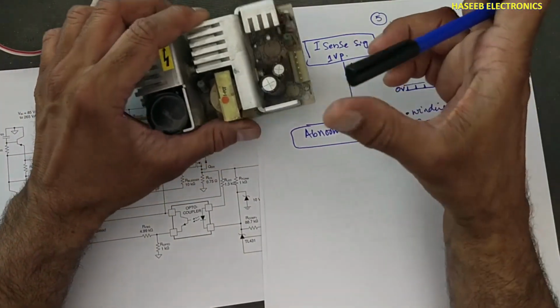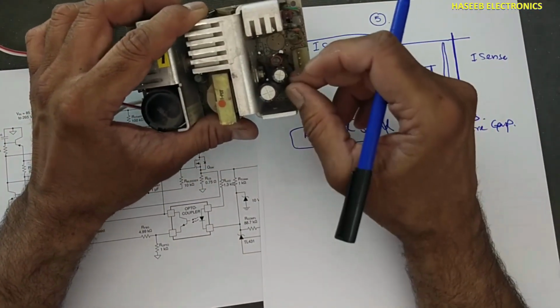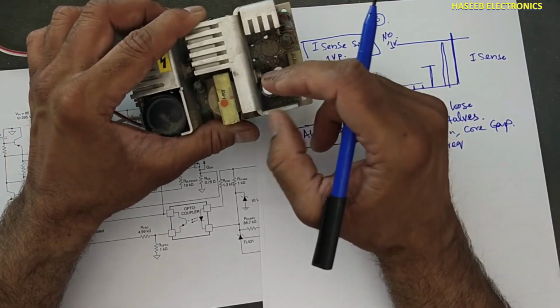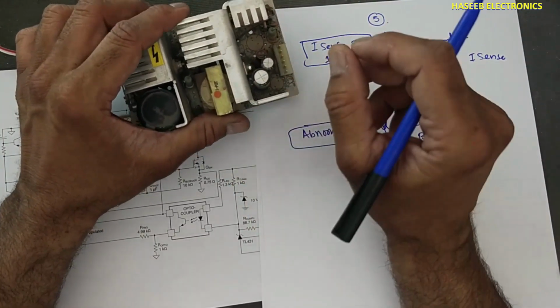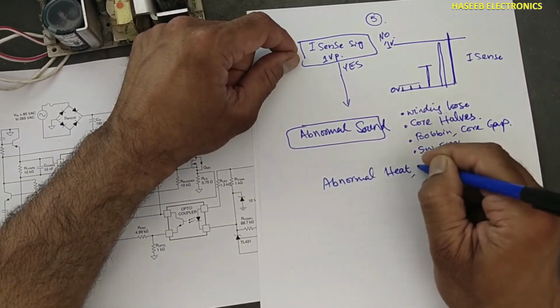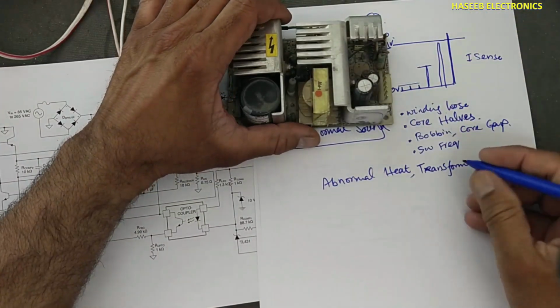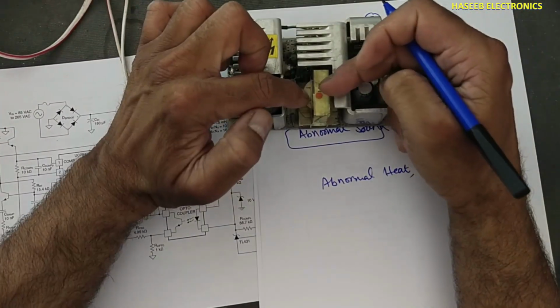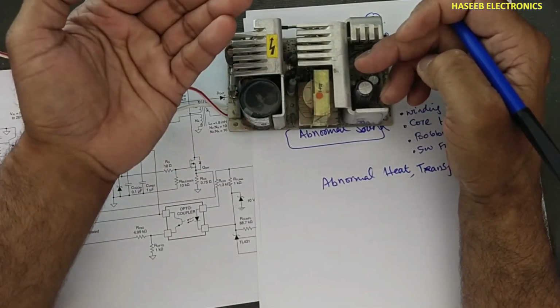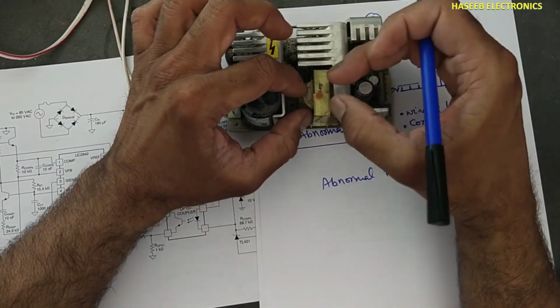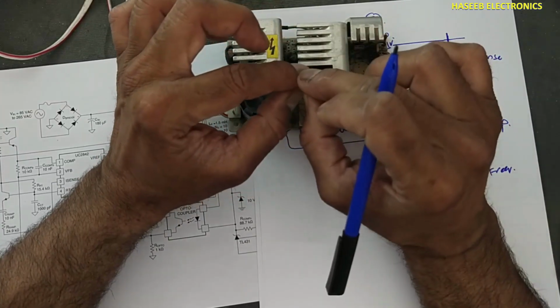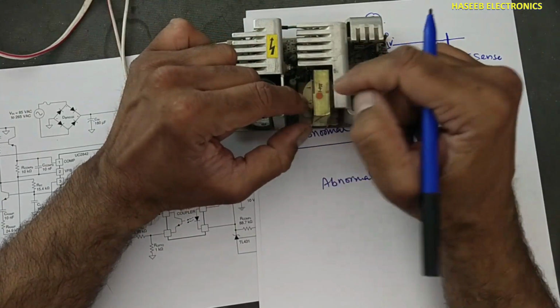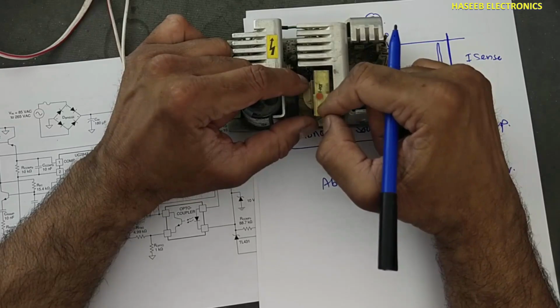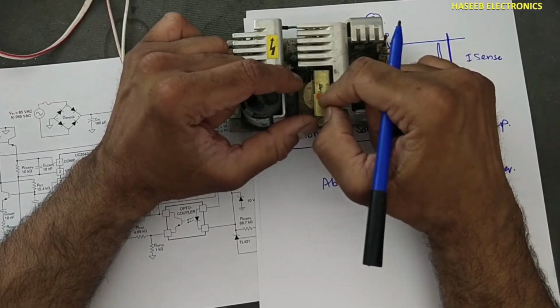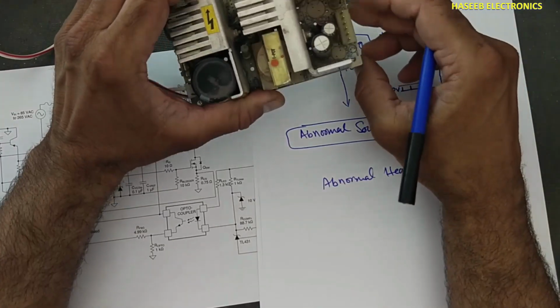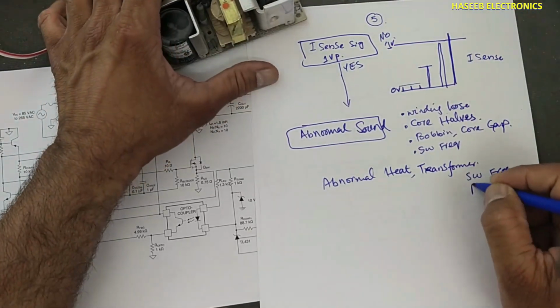If there is any capacitor short circuit in the output area, that is leak, that time it will create a hum sound. Then abnormal heat in the transformer, the most probable cause is switching frequency. If the switching frequency is less or more, it will saturate the core, because a high frequency switching transformer needs a specific frequency. If the magnetizing current increases, that time it will reach saturation, so it will heat up. Then there is another possible reason, that is the RCD snubber.